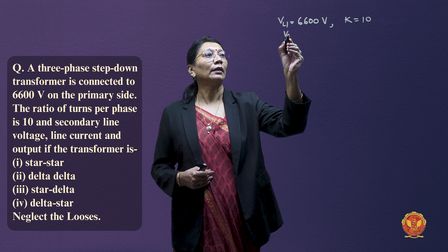Now we start the first connection, which is star-star. When both primary and secondary windings are star-connected, the line current equals the phase current and the line voltage equals √3 times the phase voltage on both sides. Since primary line voltage is given as 6600 V, the primary phase voltage is 6600 ÷ √3 = 3810.51 volts.